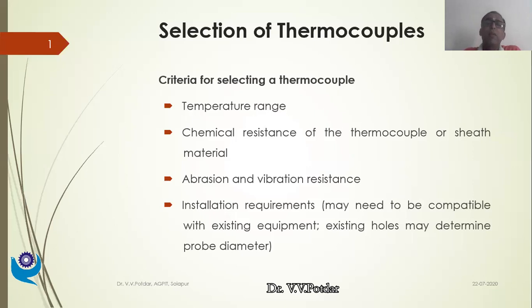Now we saw the thermocouple, which is based on Seebeck effect. If you have a dissimilar metal pair, and if you can maintain two junctions, one at hot bath and the other one at reference temperature, so to say, if we provide a temperature gradient between these two junctions, an EMF is induced in the external circuit, and that EMF or voltage can be measured and it can be correlated with the temperature difference. So this was the principle we studied.